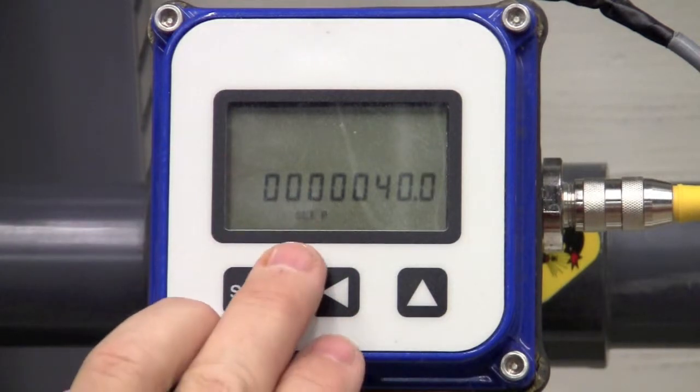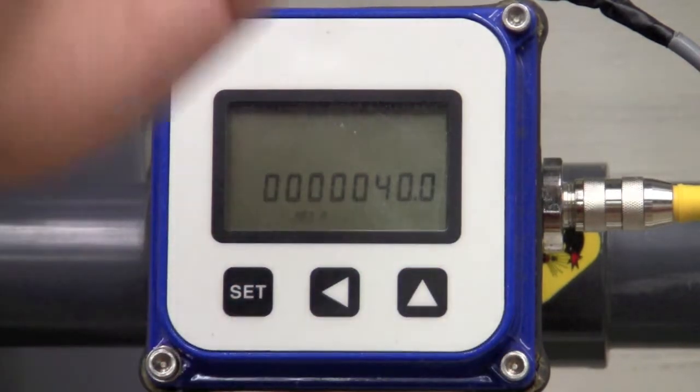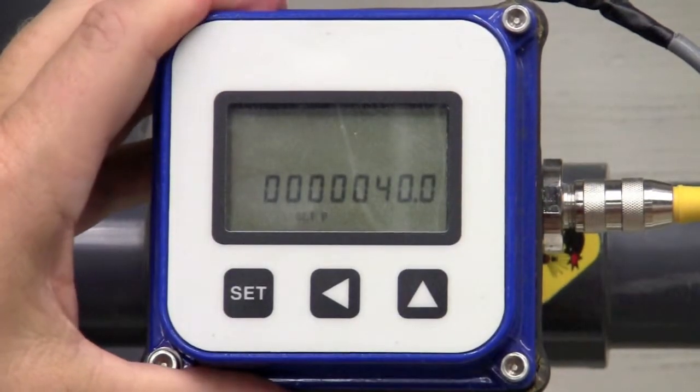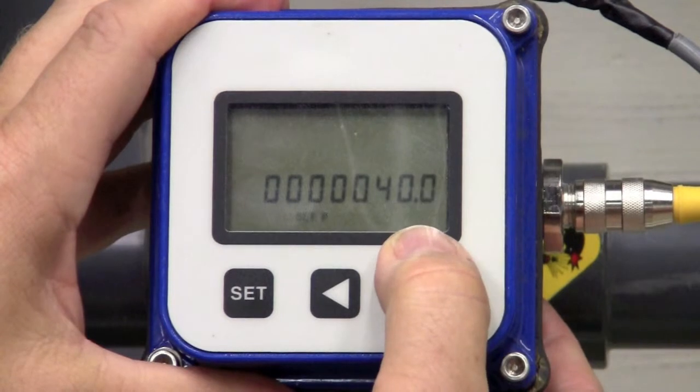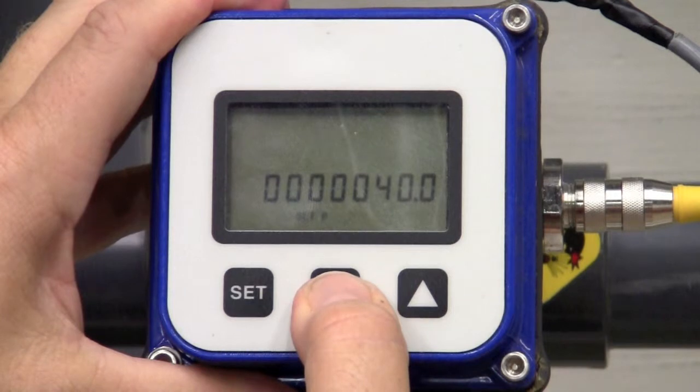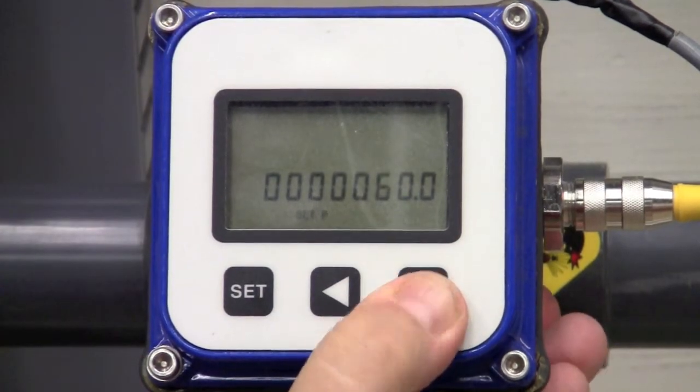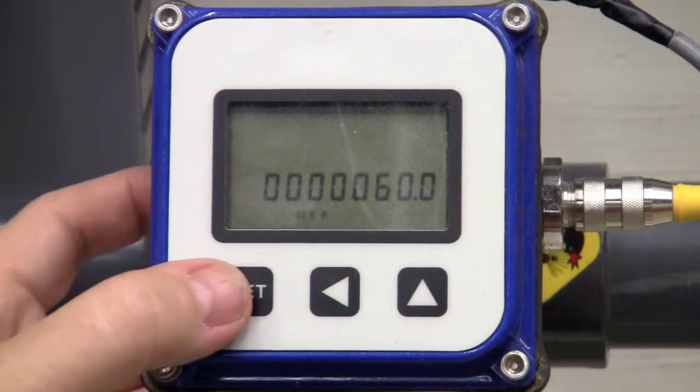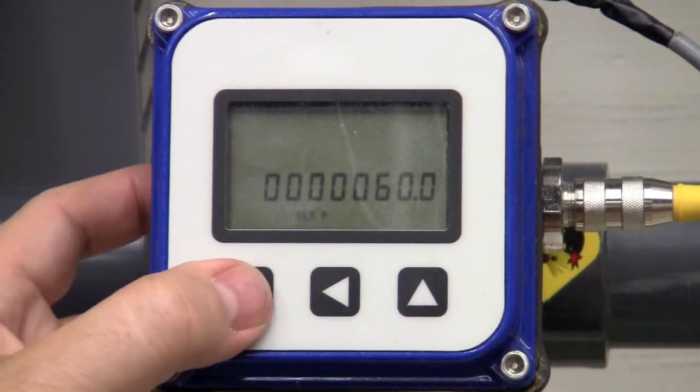It'll drive into the next parameter. The next parameter is Set P, and that's if you're using the pulse output. You can set the number of pulses per gallon. Let me set that to 60 as well. Again, the far right digit is flashing. I use the left arrow key to move it over. Once I get it to that digit, I can hit the up arrow key, and put in 60, and that's how you key it in. Once you're done with that parameter, you hit Set.